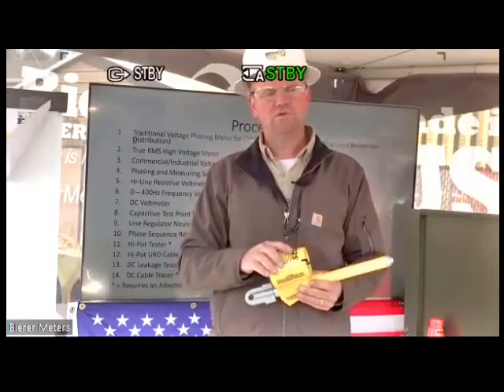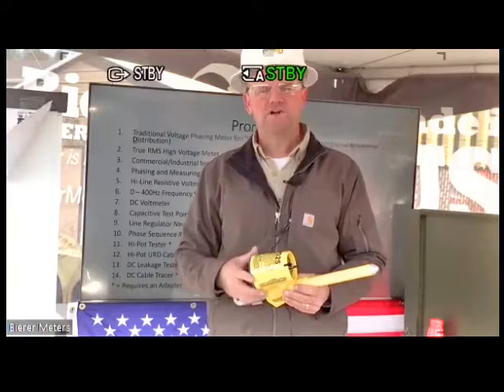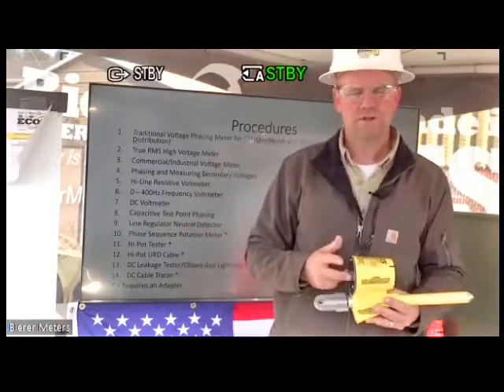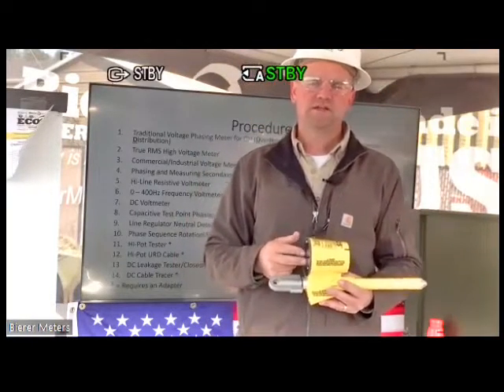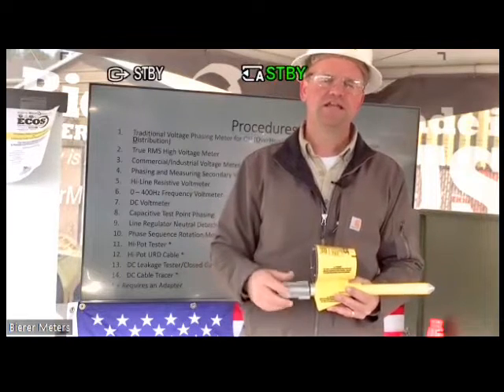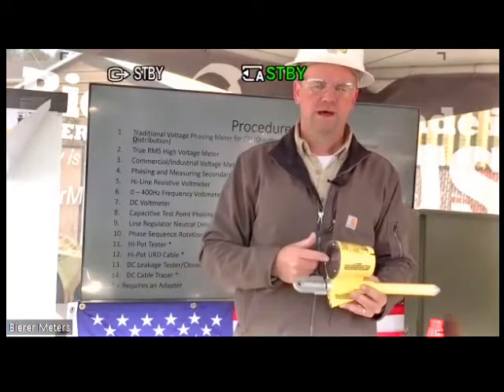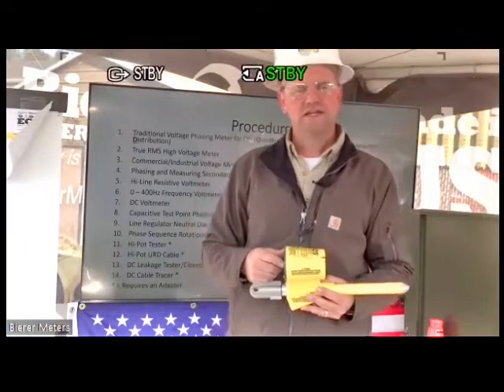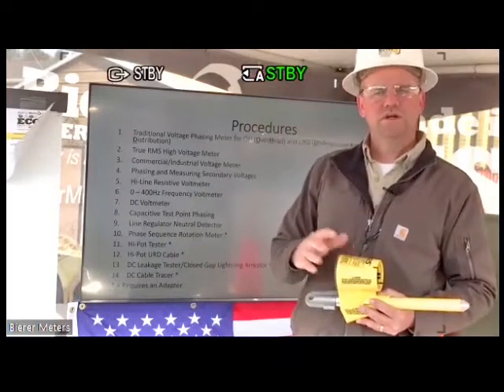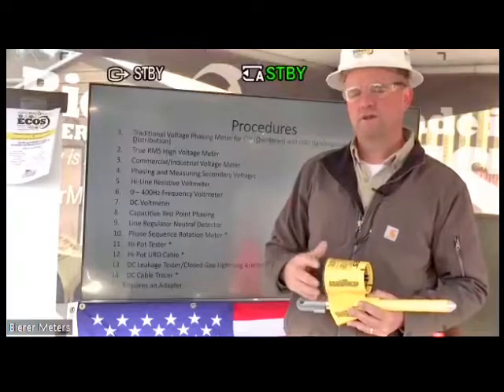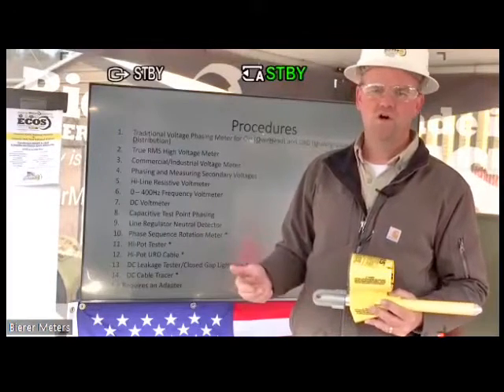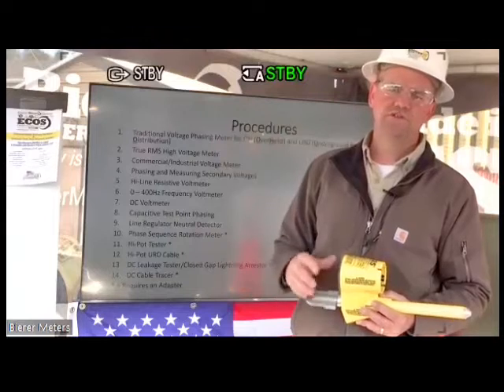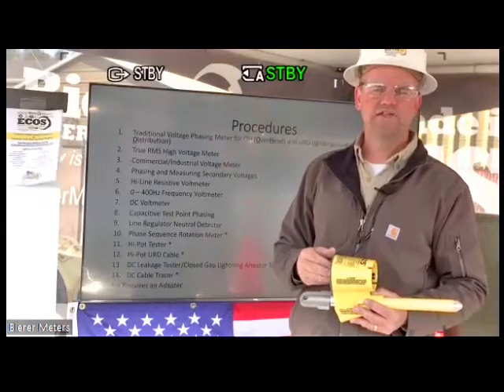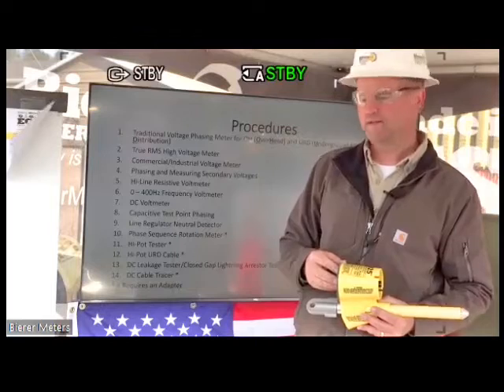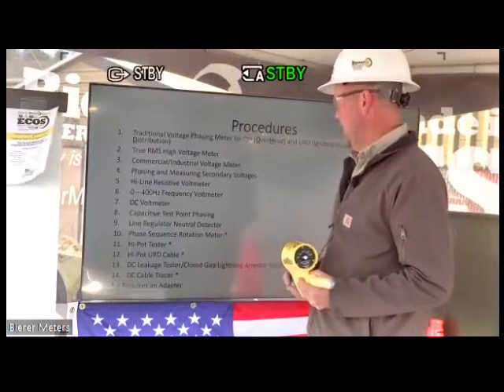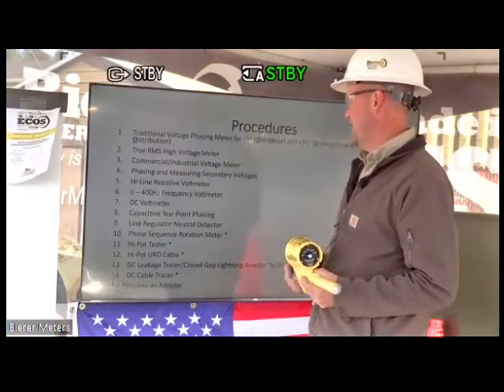With the accuracy of this tool, for every microamp of leakage on that cable, it will be displayed as 50 volts on this display. So I can actually determine how much leakage I have on that primary cable by what the display tells me. With the accuracy built into this tool, it gives you much more information. You can determine if the cable is going bad, it's getting old, or maybe it's a really long cable, so it inherently has more leakage. You'll see that on the display. A Hi-Pot URD cable, we just talked about that.